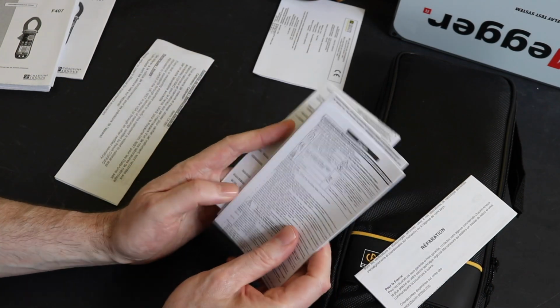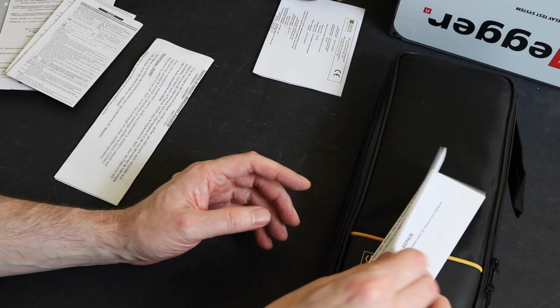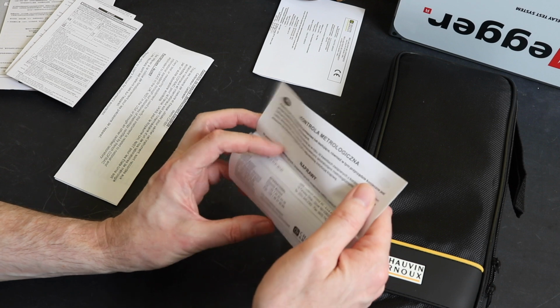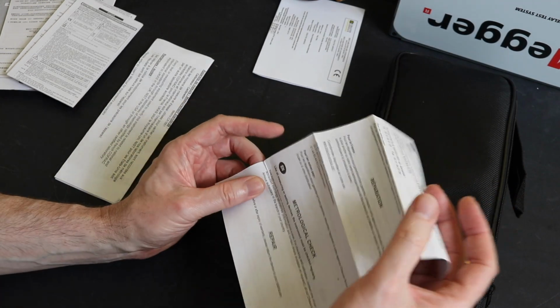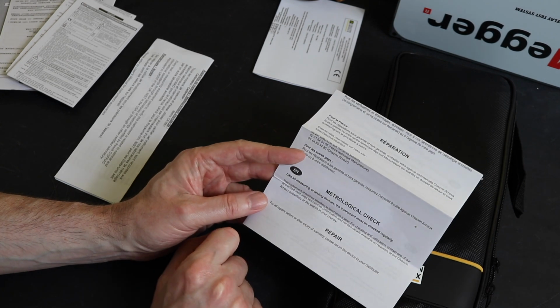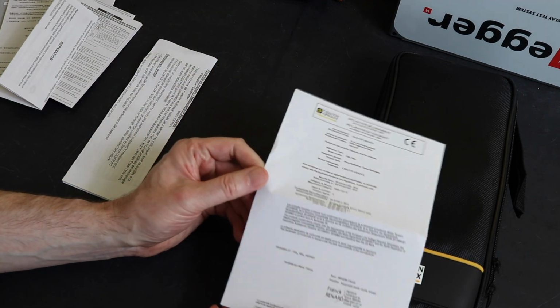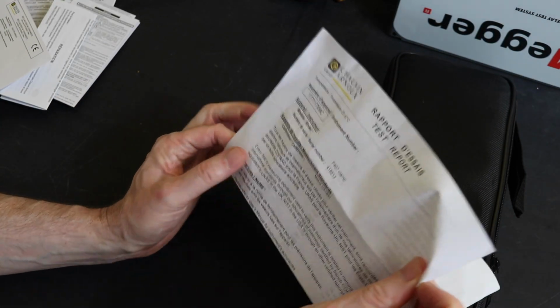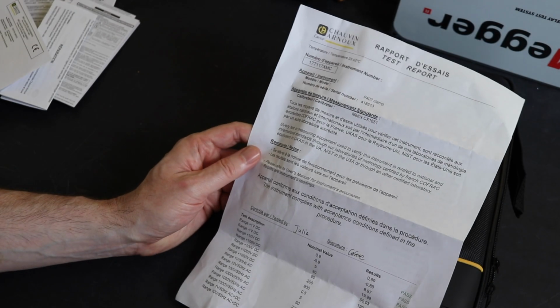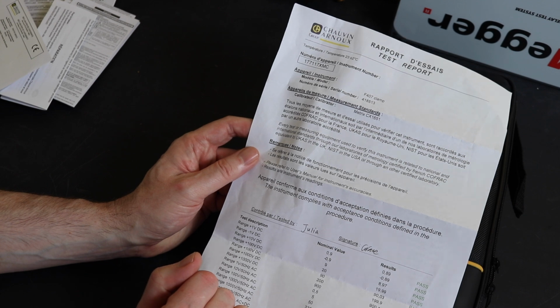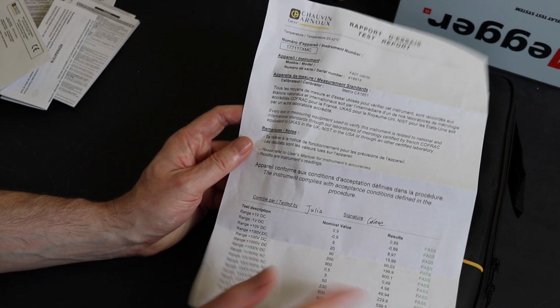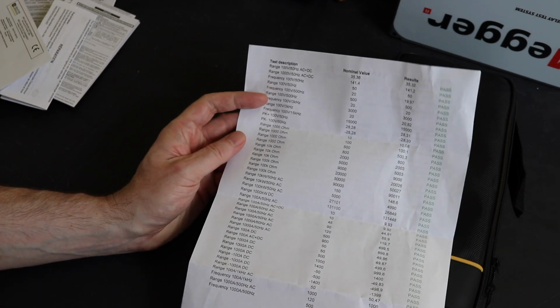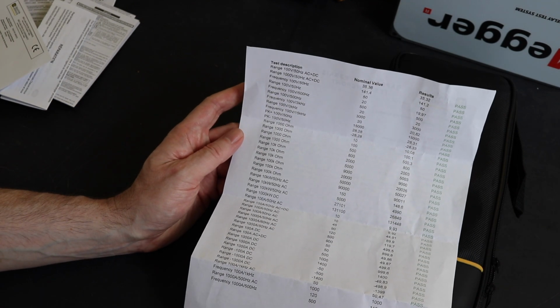You then get some basic safety sheets. These are for the test leads. All multiple languages on the same sheet for each one of those. We get, I'm not sure why this is included really, just appears to be a confirmation of the metrological check. They recommend a 1-year calibration. And then you get a certificate of conformity, that's with the CE marking nowadays, and you do get a wee little calibration certificate. This isn't dated, so you don't know when it was actually calibrated. But we've got set values in there, nominal and results, pass or fail. Obviously they are all passed, so a fairly comprehensive test there.